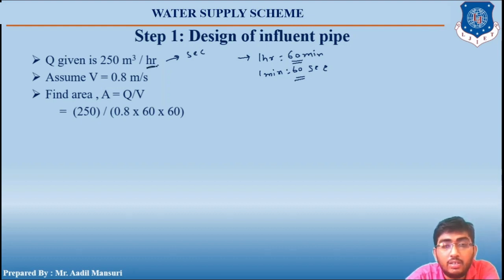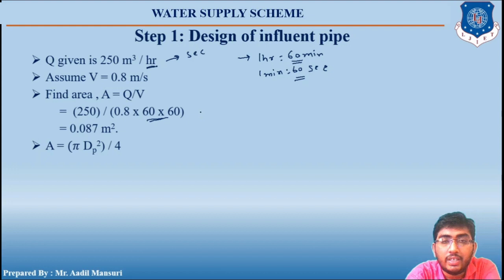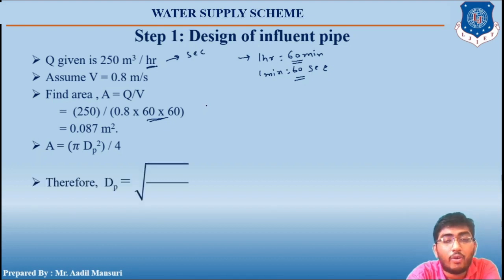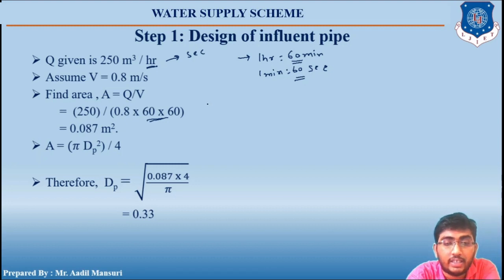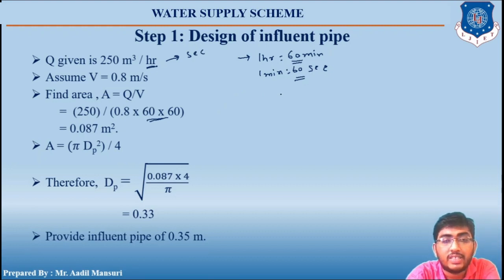Since the hour is in the denominator, we multiply by 60 × 60. So A = 250 divided by (0.8 × 60 × 60) = 0.087 square meters. Using A = (π/4) × dp², we get dp = √(0.087 × 4 / π) = 0.33 meters. Since no standard pipe of 0.33 m diameter is available, we round up and provide an influent pipe of 0.35 meter diameter.